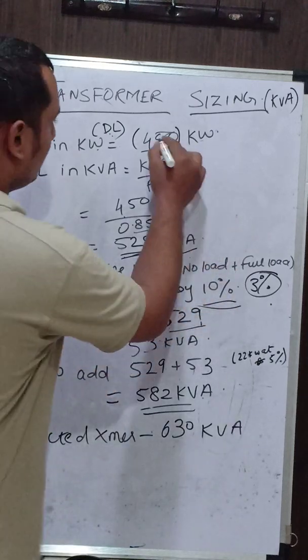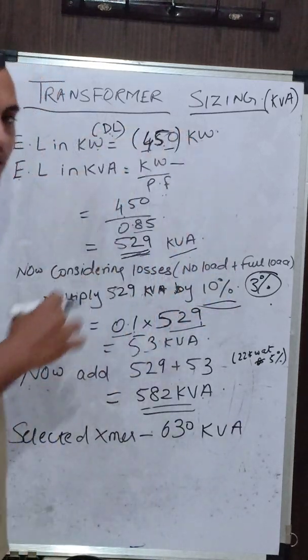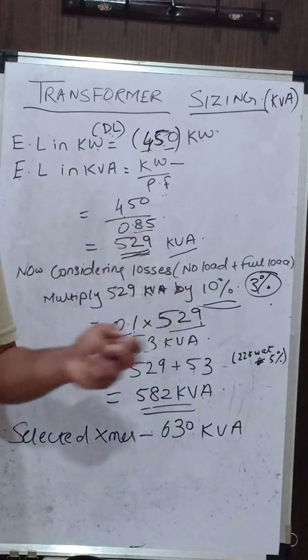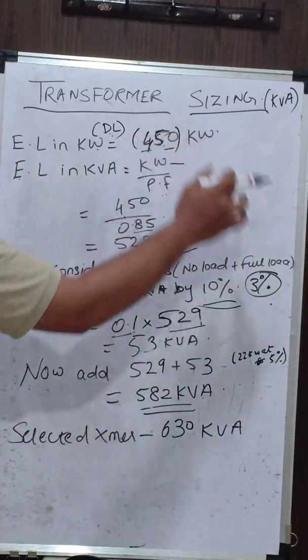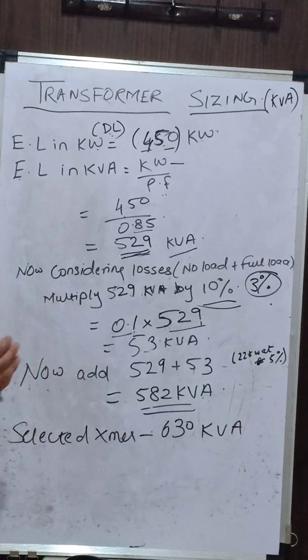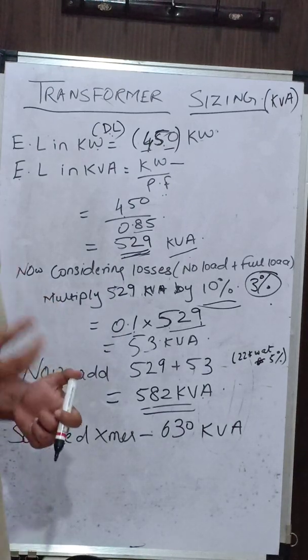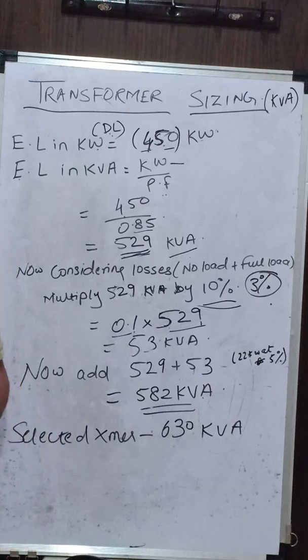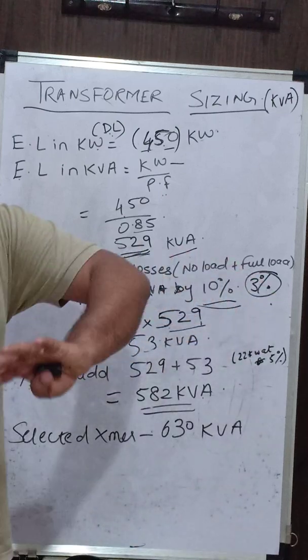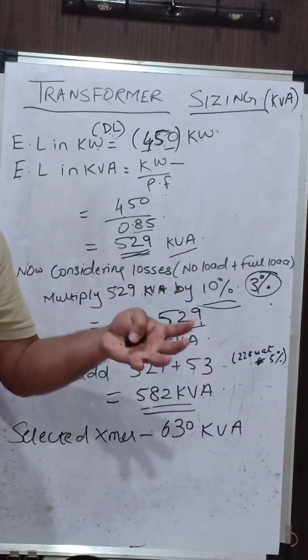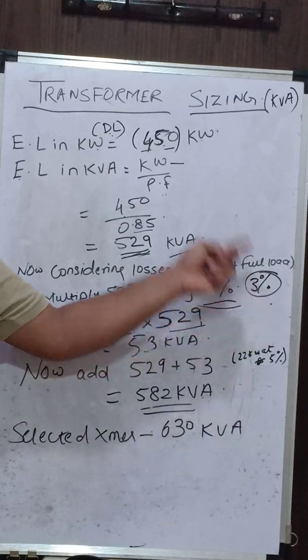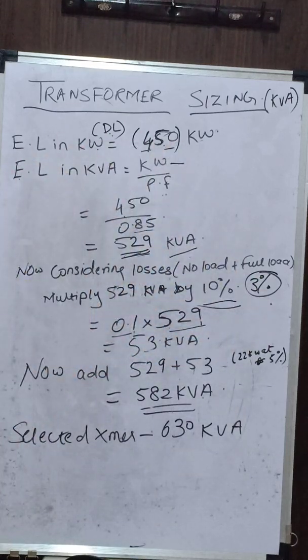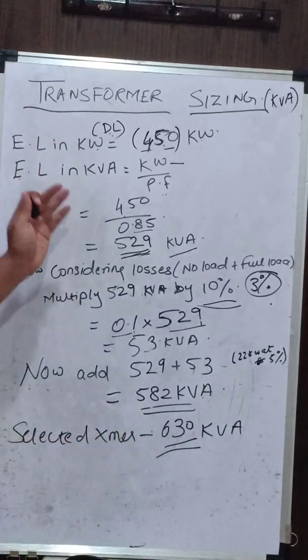The remaining 7% beyond the 3% loss allowance serves as a buffer for future load growth. For example, we considered a total electrical load of 450 kW. If in the future the client adds some electrical load to the residential building, approximately 5% of the total load — about 22 kW — the transformer still has the capacity to feed that additional load. So the 10% breakdown is roughly 3% for losses and 5-7% as a buffer for future increases. The selected transformer is 630 kVA.